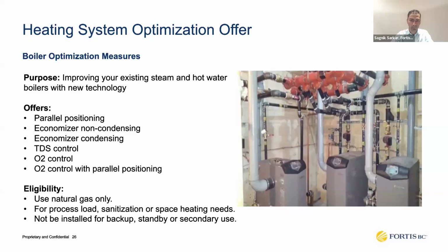Next is O2 control. Oxygen control is like adjusting the oxygen by checking the flue gas. If you have excess oxygen in your flue gas, you are wasting heat, which means the burner is not combusting the natural gas efficiently. A flue gas monitor at the exhaust of the furnace or the boiler measures the oxygen level and reduces or increases the oxygen proportionally to maintain optimum combustion. And finally, oxygen control with parallel positioning combines the benefits of both of these measures into one single measure, and again, the incentive is proportionally higher.